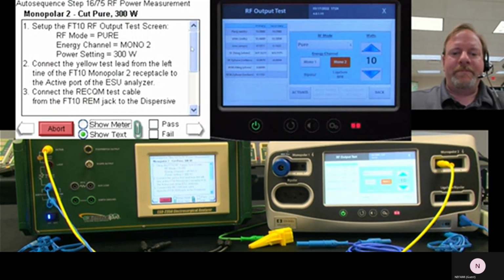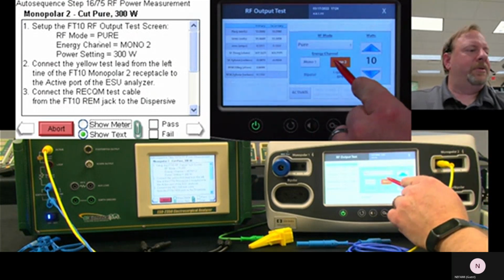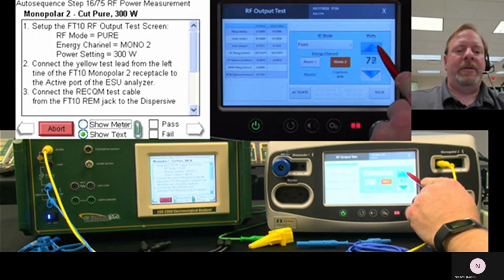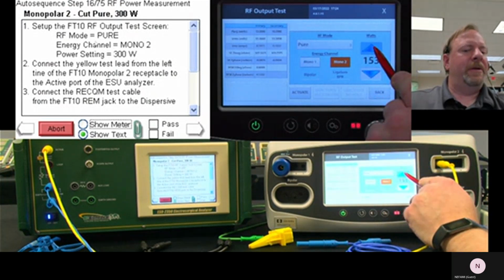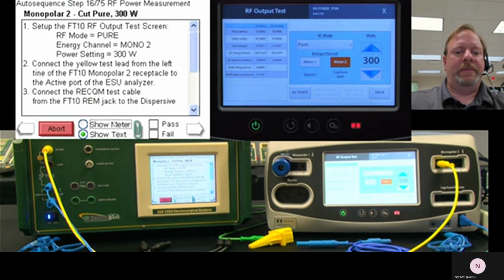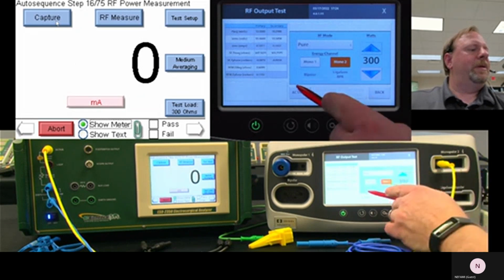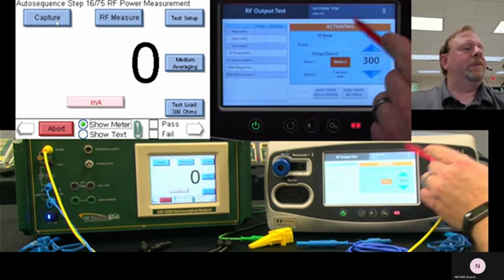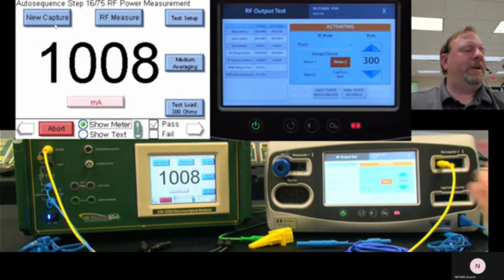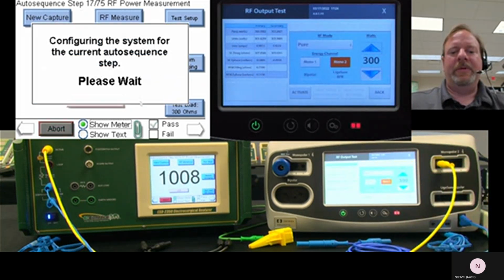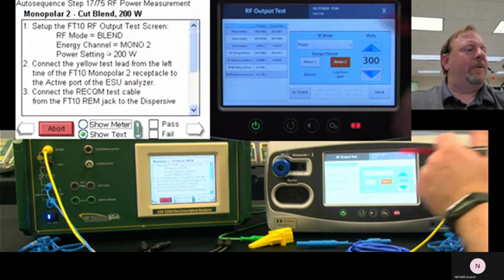So then we go in here, pure, monopolar 2, 300 watts. So the nice thing here, I get my settings for the generator. I get my wire to the test. So go to show meter, activate the output, capture the reading, deactivate, move on to the next. Now we go to blend.